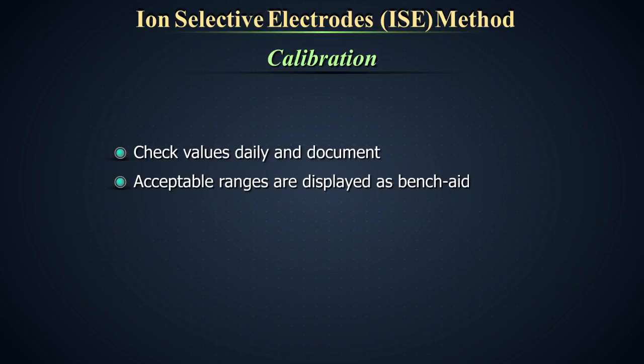Acceptable ranges should be displayed as a bench aid near the equipment to give ready reference to its performance. If the acceptance criteria are breached, perform maintenance as per manufacturer's instructions.